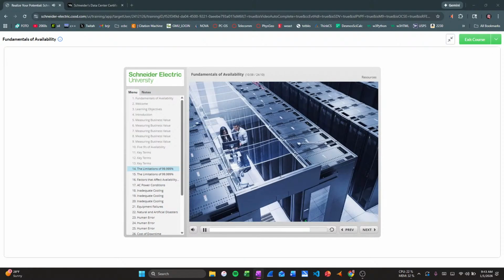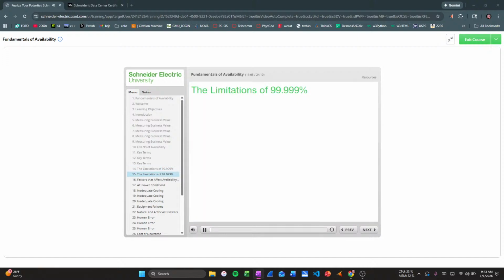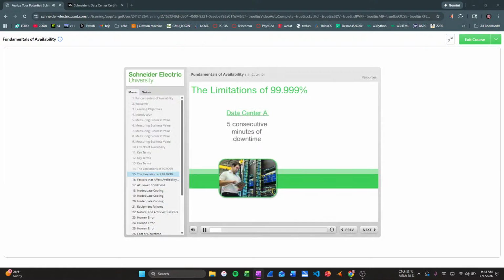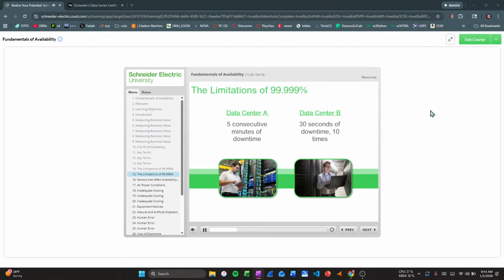The frequency of failure is only one part of the equation. The other part of the availability equation is how long it takes to recover from a failure. Let's take, for example, two data centers that are both considered 99.999% available. In 1 year, data center A lost power once, but it lasted for a full 5 minutes. Data center B lost power 10 times, but for only 30 seconds each time. Both data centers were without power for a total of 5 minutes each.